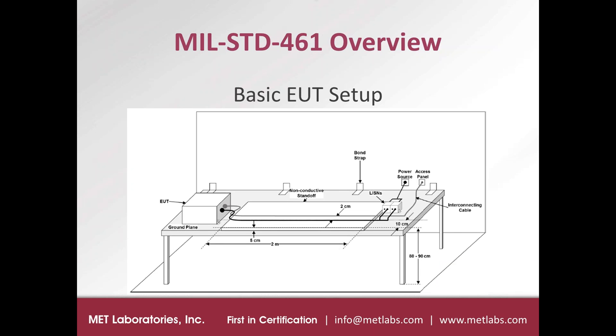And then the next step is to make sure that your EUT is first set up for the basic setup requirements that appear at the beginning of MIL-STD-461. The basic setup is required for all the test methods. So the basic setup shows you the size of the tabletop ground plane, the height, how the EUT cables need to be arranged at different lengths, and they need to be insulated from the ground plane by 5 centimeters, and you need to have 2 centimeter separation between cables, and all these different parameters need to be achieved.